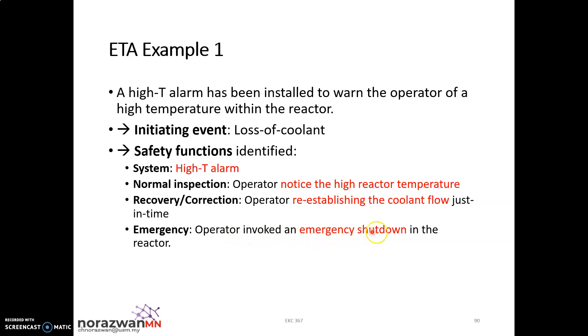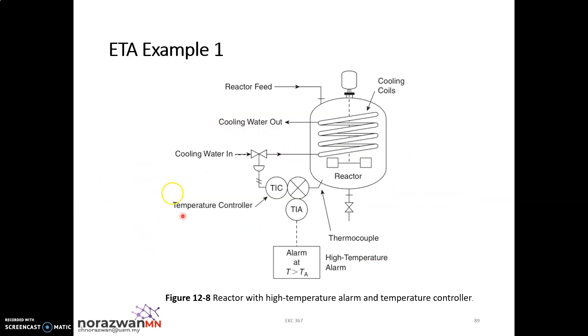The fourth safety function is emergency shutdown — the operator invokes an emergency shutdown of the reactor. So the four safety functions for this reactor are: the high temperature alarm, the operator noticing the high temperature via process monitoring, the operator reestablishing the coolant flow as the recovery/correction step, and finally the emergency shutdown.